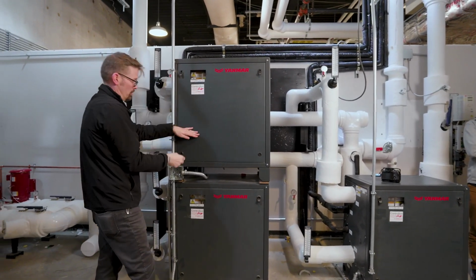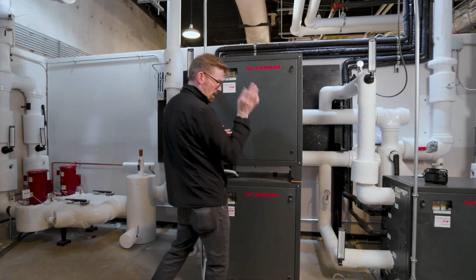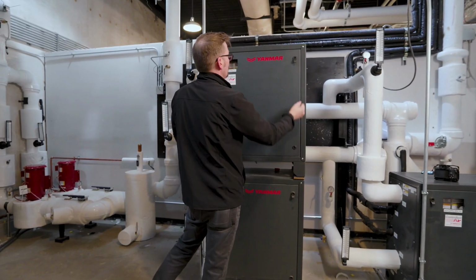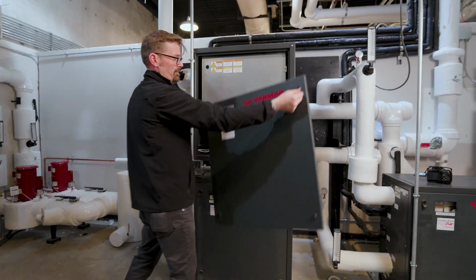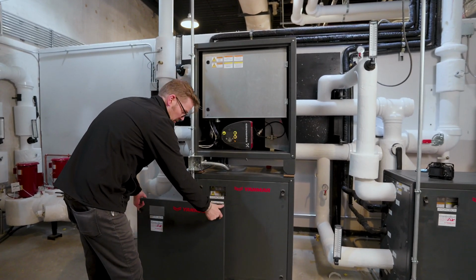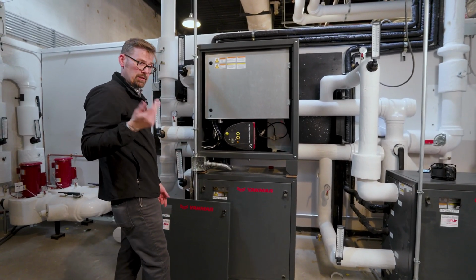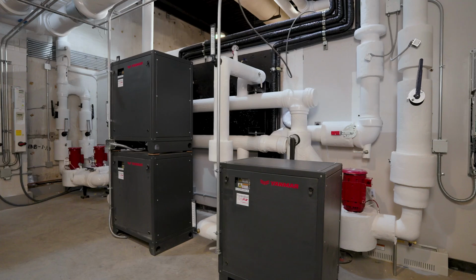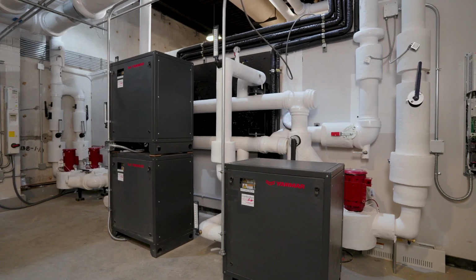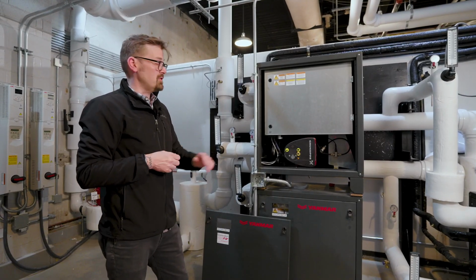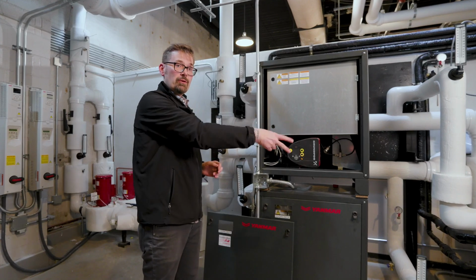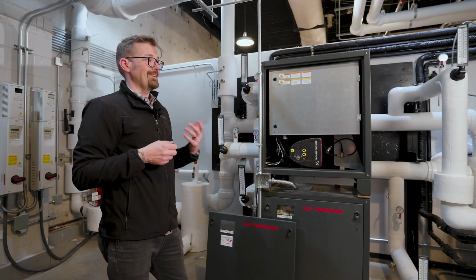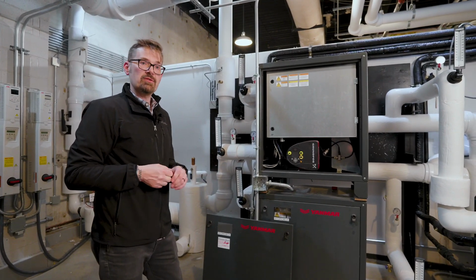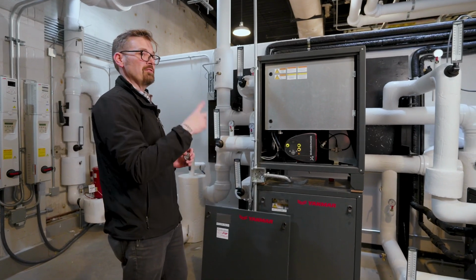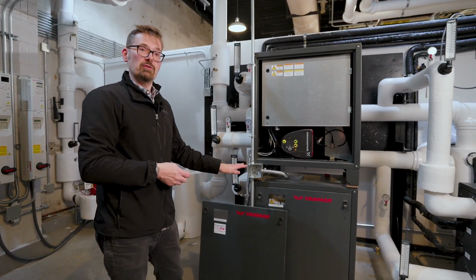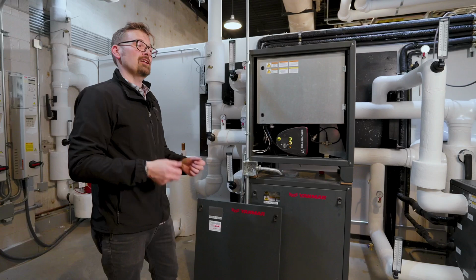These systems will allow each other. This Hydrobox will talk and communicate with the GHP outside. In fact, all three of them will communicate with each other and run each other off a lead lag. The way that these systems are designed is that 2 of these units will be able to handle the load of the system, but in case we have a failure of one, there's a third. Because we are in a critical environment within these labs, we need to make sure that there's always a safety factor of 1. In case you do have a failure, you don't have to worry about a catastrophic failure within their space also.